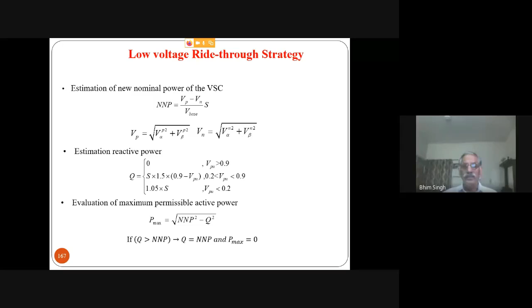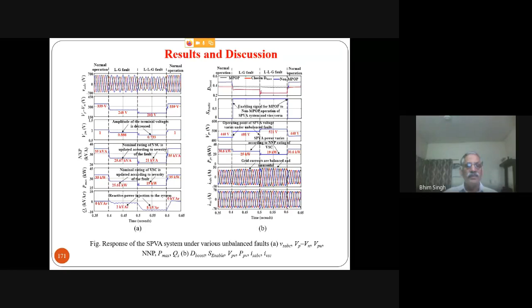Your new standard has come. In spite of a fault, you keep the inverter live, because whenever the fault is removed, you should come back into operation very quickly. So the new code says you should not disconnect the inverter when there is a fault on the grid, and when it comes back, you retrieve operation at full satisfactory level. Even during the fault, you should be able to feed some active power, and give the system reactive power, similar to FACTS devices.